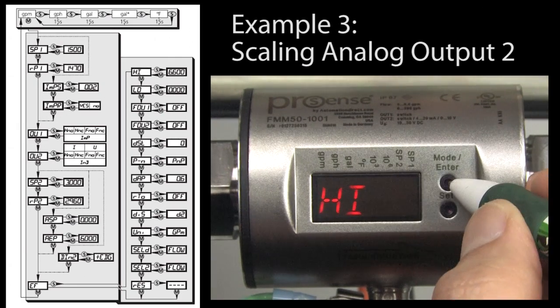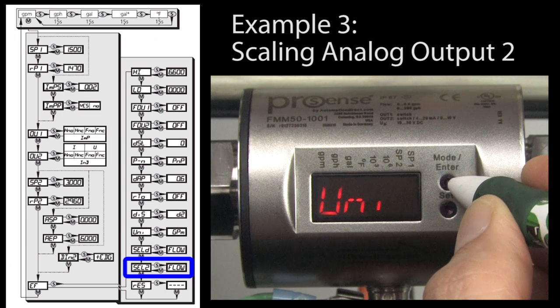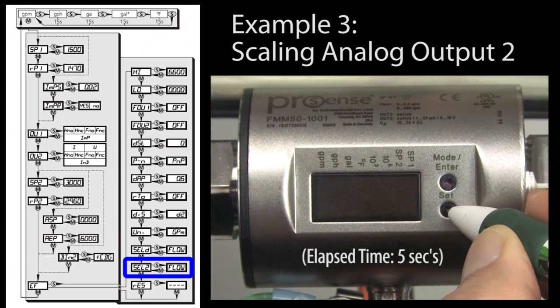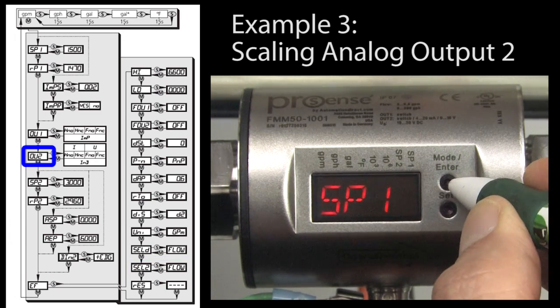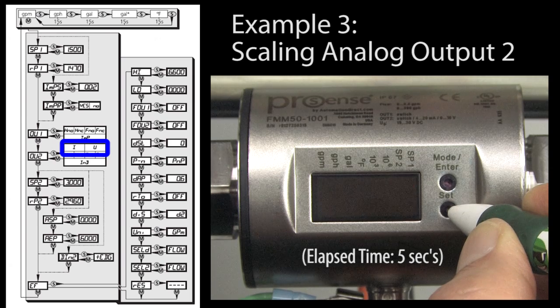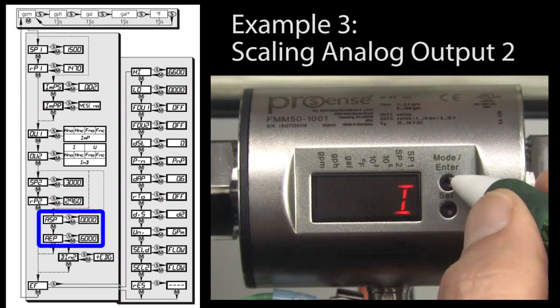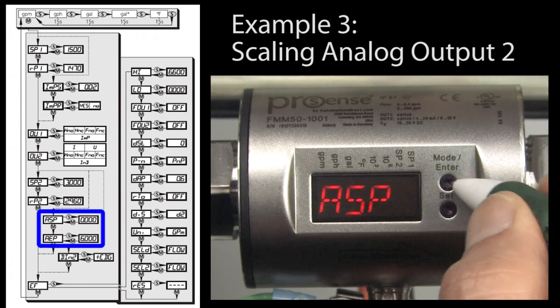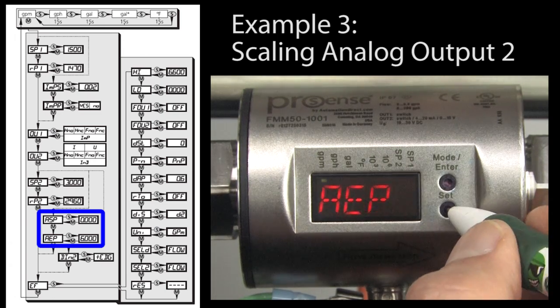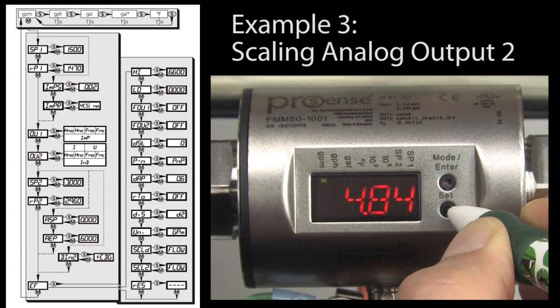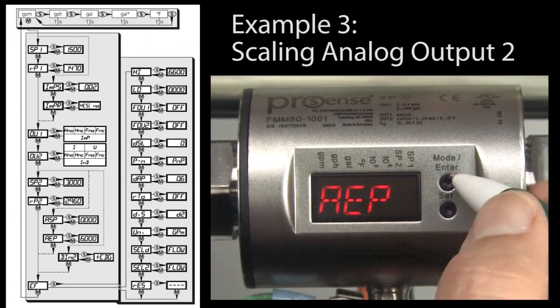To do that scaling, make sure you have the function you want selected in SEL 2 – Temperature or Flow. Then under Output 2, select if you want current or voltage output. Once you do that, these options become available – ASP is the minimum output value and AEP is the maximum output value. Well, that's all there is to scaling your analog outputs.